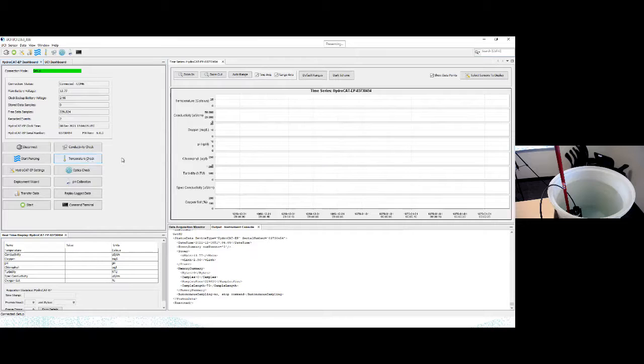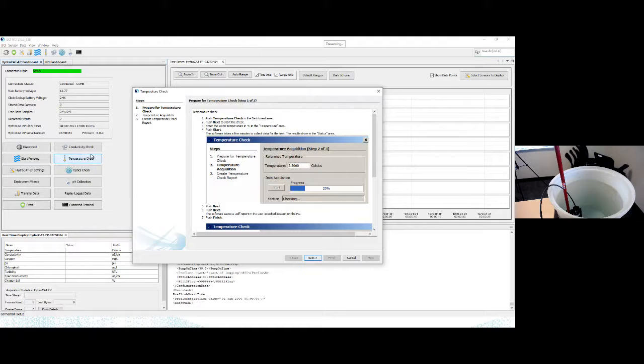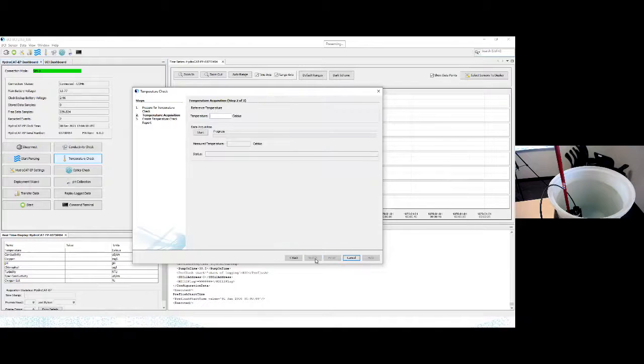In the interest of time, we won't go through the full temperature check, since my instrument seems to be responding pretty slowly right now. But if you were to do this, I'd recommend putting your instrument into a bath of water, typing in the expected value here, and clicking start. Your instrument will compare the output from your HydroCAT to the expected value you typed in, and make sure that stays stable over a couple of minutes. If it does, it'll say your temperature check passed and your temperature sensor is working as expected, and then you can move on to a different check.